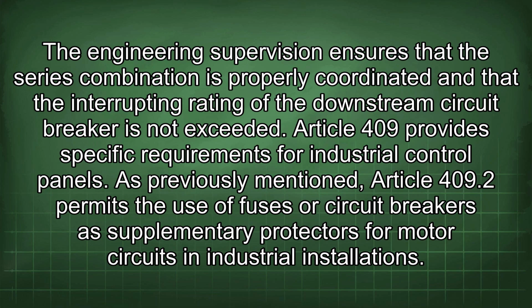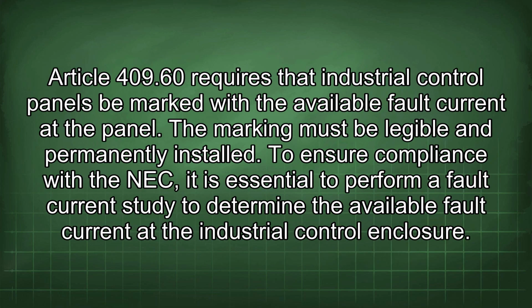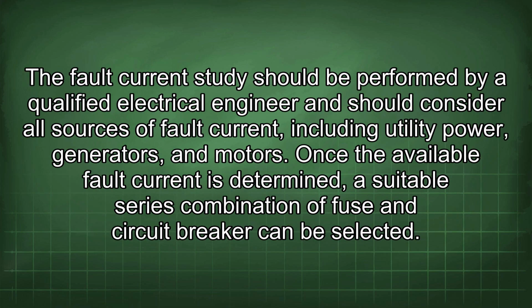As previously mentioned, Article 409.2 permits the use of fuses or circuit breakers as supplementary protectors for motor circuits in industrial installations. Article 409.60 requires that industrial control panels be marked with the available fault current at the panel. The marking must be legible and permanently installed. To ensure compliance with the NEC, it is essential to perform a fault current study to determine the available fault current at the industrial control enclosure. The fault current study should be performed by a qualified electrical engineer and should consider all sources of fault current, including utility power, generators, and motors.